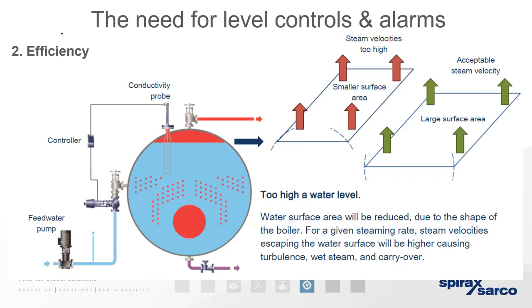That is, using heaters or using indirect heating of RO water with plant steam? So I'm actually going to pose that question to Alvin, because he's a boiler manufacturer. It will also depend a lot on the style of the boiler you have. But Alvin, can you grab that? Thank you. Sorry again. So for pure steam, the best method will also be dependent on, as I said, as was hinted, the setup, whether you're using heaters or you're using process heat. So it's usually dependent on how the setup is. So there is no, let's say, one rule that fits all.